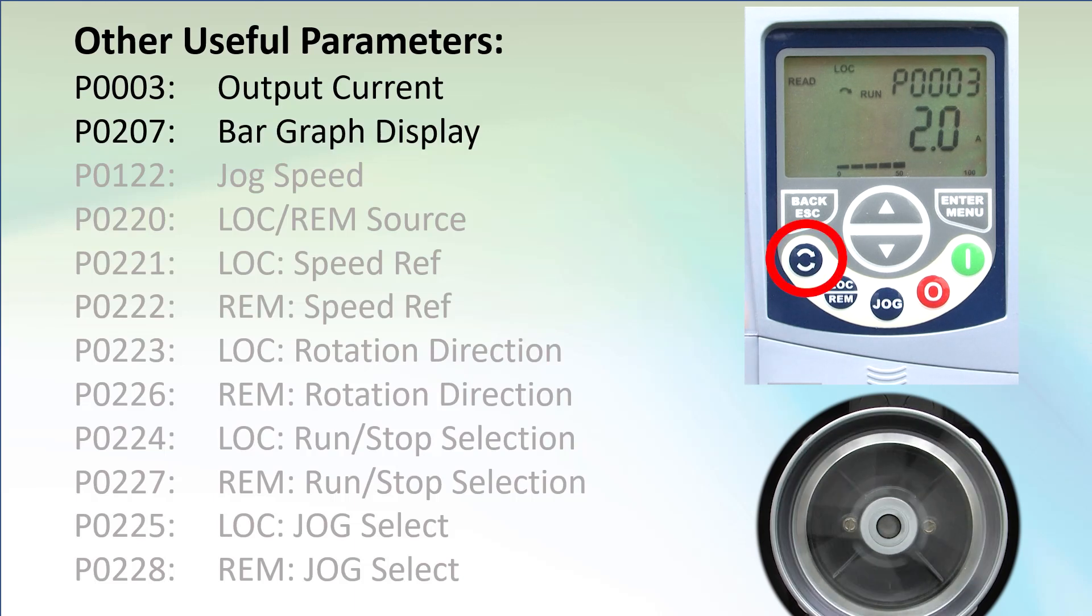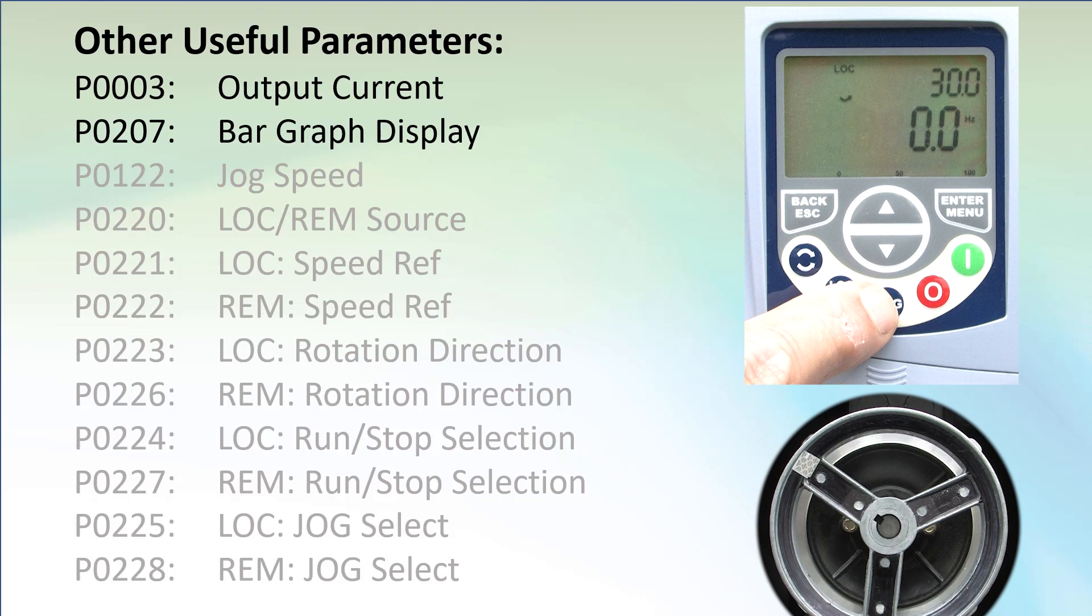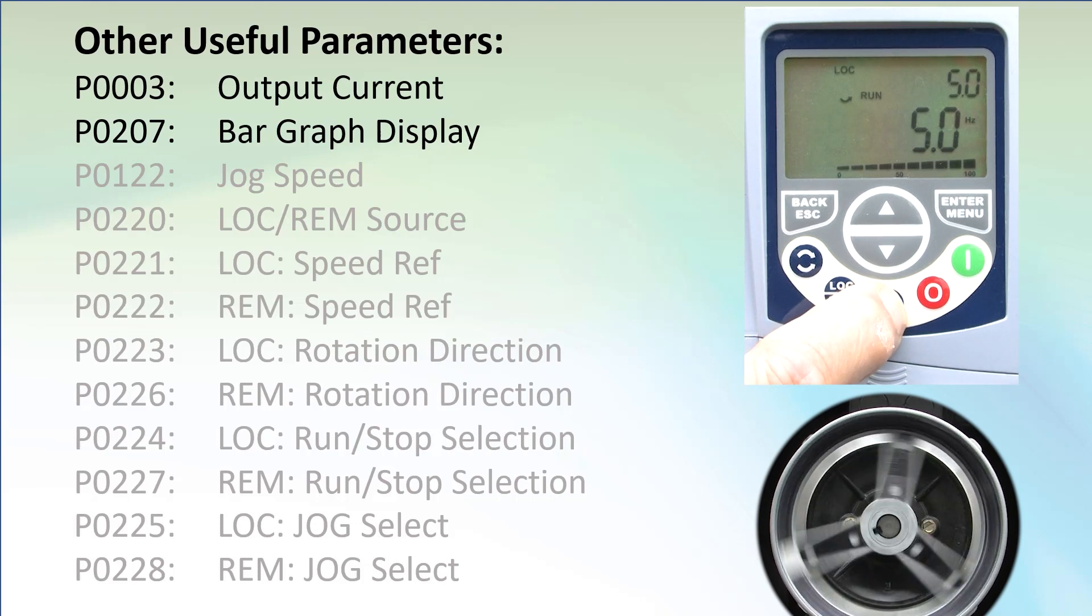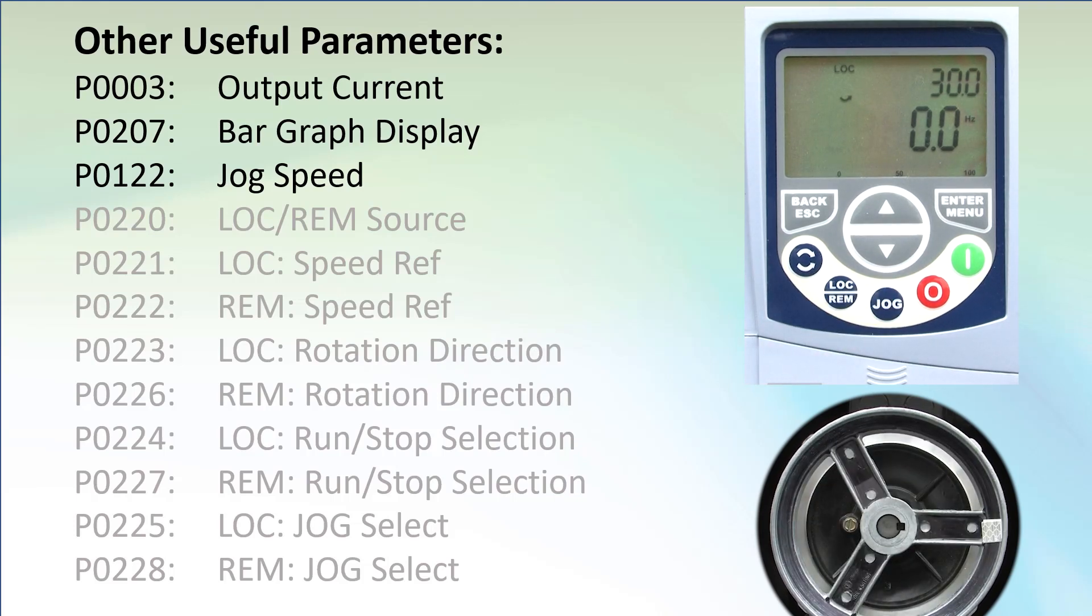Forward and reverse is controlled by this button. The motor ramps down and then back up in the other direction. Let's stop the motor and escape back to the top level menu. If I hold down the jog button, the motor moves at whatever speed you put in the jog reference frequency at parameter 122. The default is 5 hertz. And I love that you can switch between local and remote right here on the keypad.